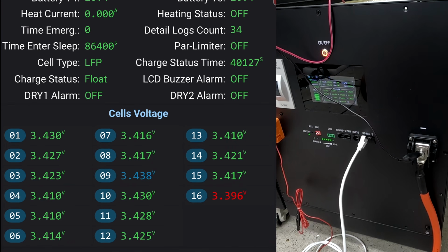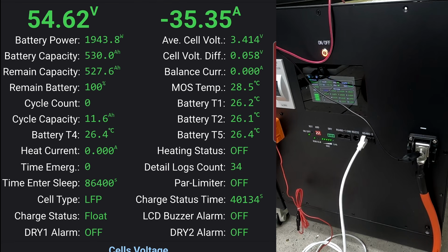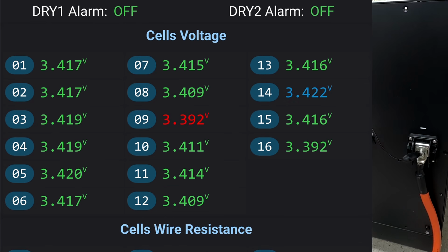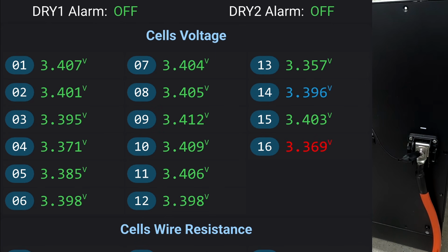Okay, let's leave it running. Checking on the BMS, we've got a cell deviation of 58 millivolts, which is quite high for such a small current. Cell number 9 is our lowest - now cell number 9 is our highest. Once an inverter is connected to the JK BMS, you can't read any voltages properly anymore. Look how they go up and down all the time, so it's very hard to pinpoint the highest and lowest cell here.